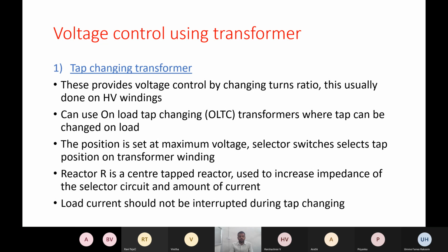And also the HV winding is wound outside the LV winding. Because of this characteristic, the HV winding is placed outside the LV winding, so that's why it is easy to tap, and that's why we go for the HV side of tapping. The connections are of two types, one considering the load and one without considering the load. This tapping at the HV winding is the same for both transformers. The tappings will be at the HV winding only, for on-load tap changers and also off-load tap changers.